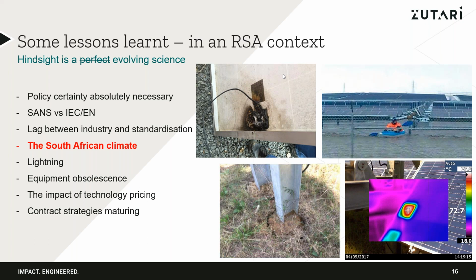And with that is lightning. Lightning damage in South Africa, specifically in the northern parts, is very significant, with upwards of 10 to 11 strikes per square kilometer per annum. We're talking about severe lightning, and unfortunately a PV plant is really just one big lightning conductor. So making sure we limit or isolate the damage as much as possible with an appropriate lightning protection system design is absolutely required, done upfront, with equipment specified correctly.